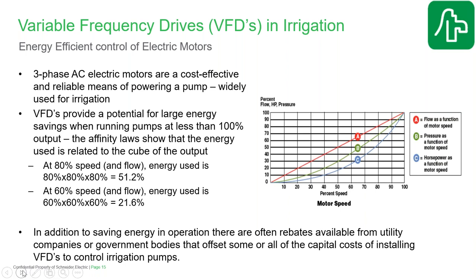So if you're reducing the output of the pump from 100% to 80%, you're not really reducing the energy use to 80% of what it is. You're reducing it by 80% by 80% by 80%. So you're saving close to 50% of the energy. If you're dropping that output to 60% instead, you're saving close to 80% of the energy. It's because of this cube relationship. So because of this, the use of VFDs is extremely attractive from a point of view of reducing the cost of ownership of the pump system.